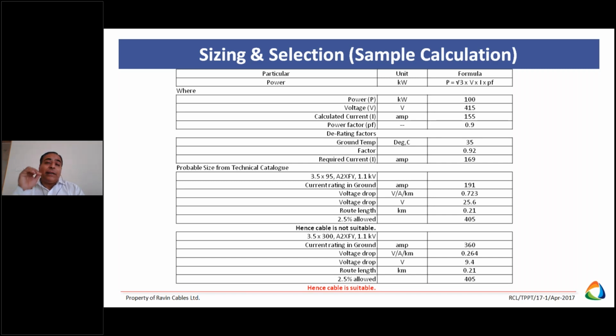Now here, the very important part is what? What are your design parameters? What is your safety factor? Ultimately we are talking about the reliability of the system, and energy saving or energy conservation. If cables are not selected as per the requirement, this leads to higher losses. Basically, we are discussing the transformer losses, but nobody is discussing the losses in the cables.